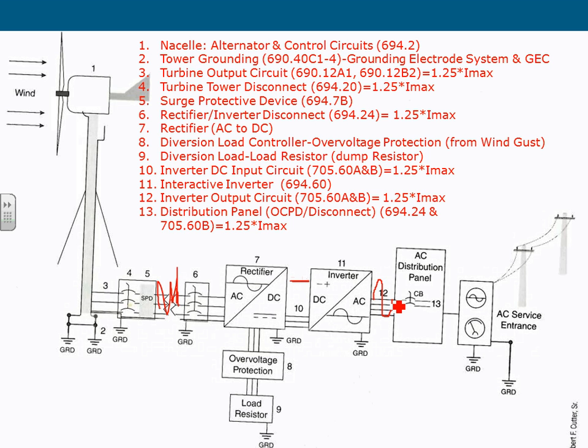This is an interactive inverter, meaning it is synchronizing with the grid. It will be interactive if you have a grid. In this case, we do have a grid, so this has to be an interactive inverter. And that's where we're getting into the detail now.